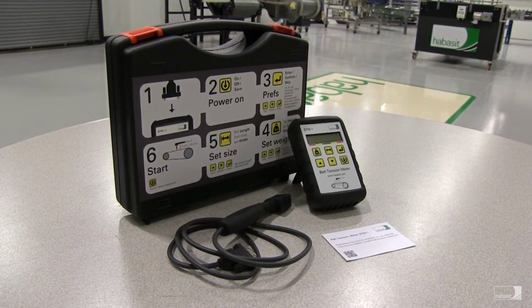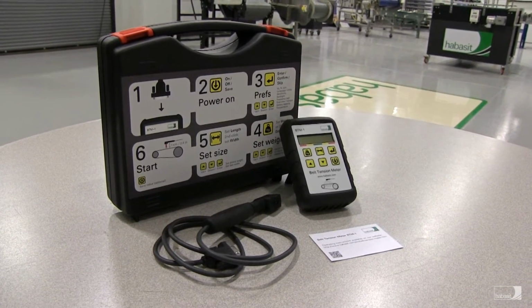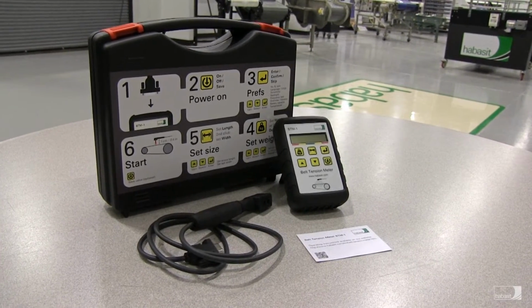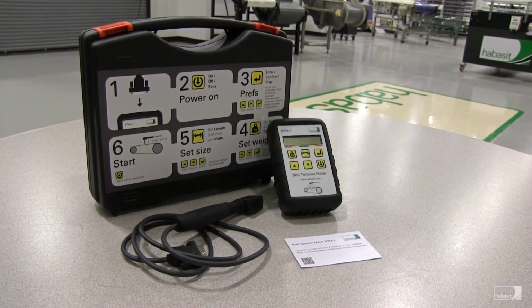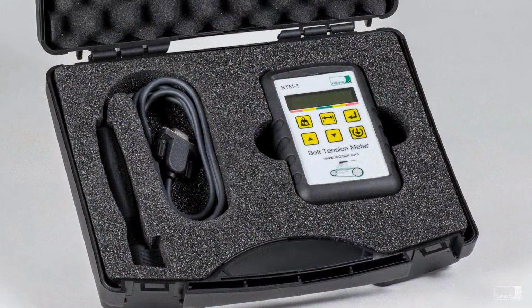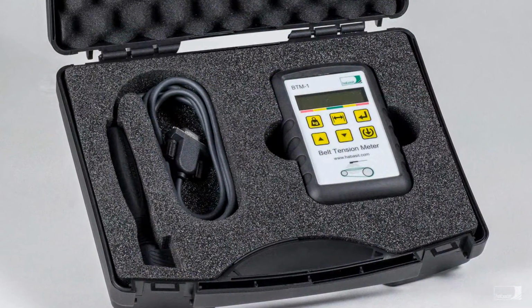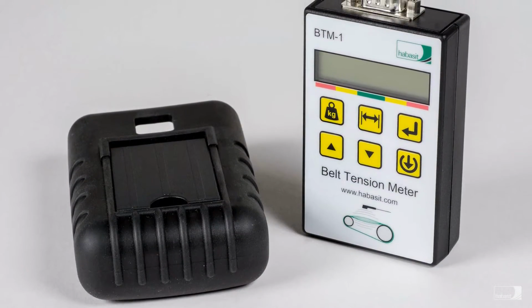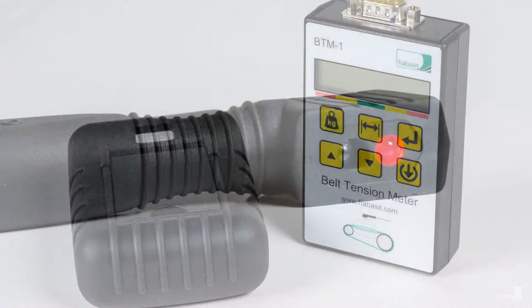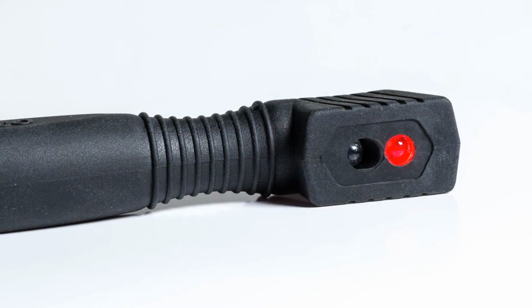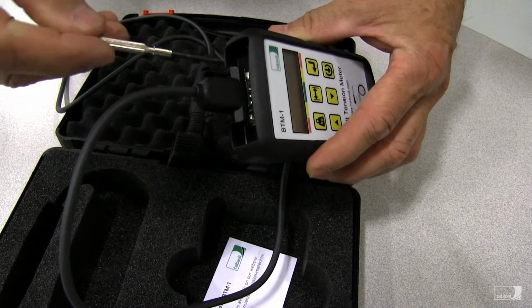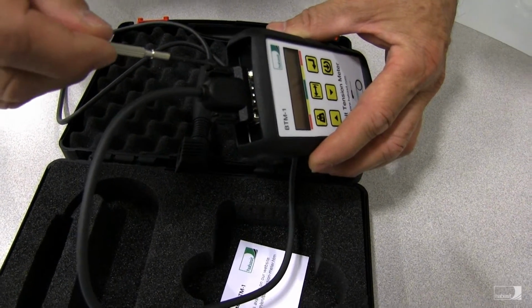This is a brief overview of the operation of the Habasit Belt Tension Meter BTM-1. The belt tension meter consists of the meter itself, which is covered with a durable rubber cover for protection of the instrument, and the sensor probe. The measuring probe plugs into the top of the unit and is secured with 2 screws.